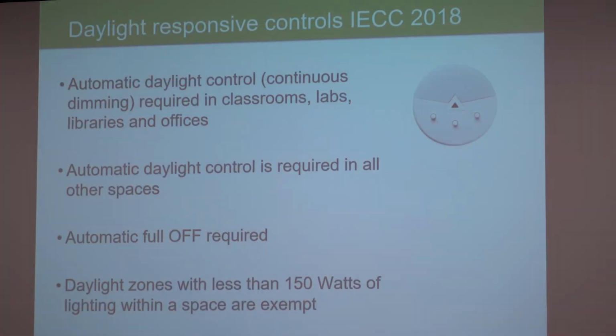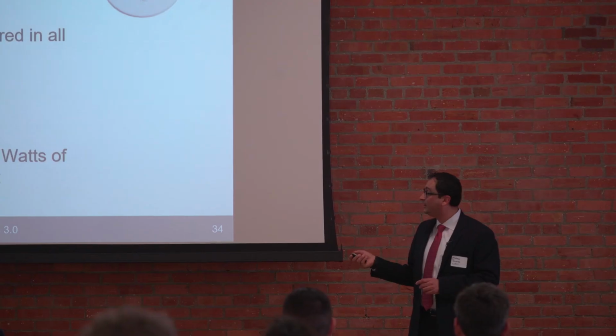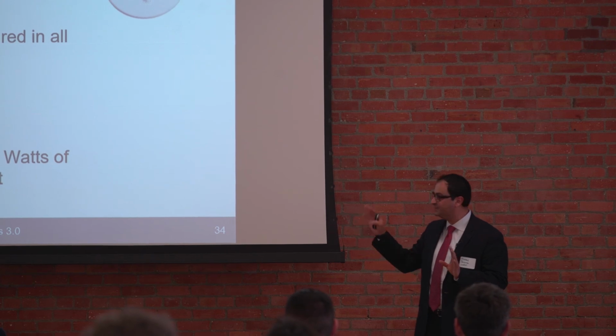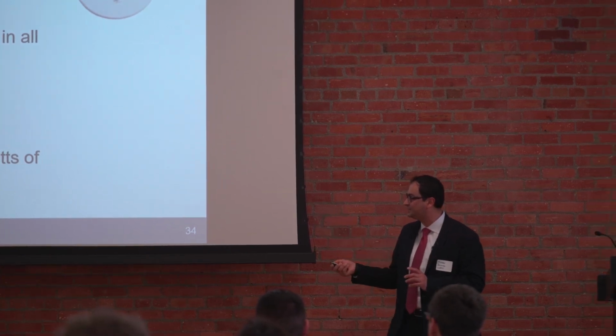IECC actually requires continuous daylight dimming now in classrooms, laboratories, libraries, and offices. It's actually more stringent than ASHRAE, which technically doesn't require continuous daylight dimming. Daylight dimming complies, but you only need like 3 levels to comply. But in those spaces, you have to do continuous daylight dimming. Automatic daylight control, even if it's not dimming, is still required in all the other spaces.